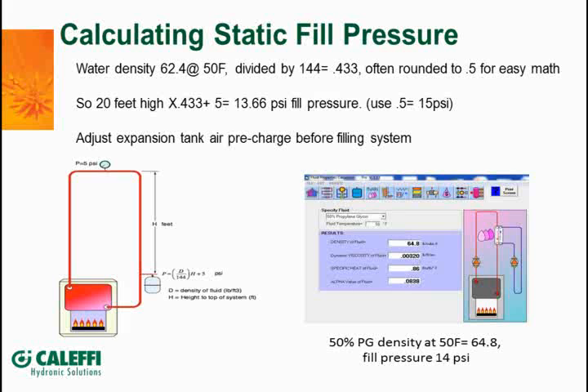You're not using the pump. Your circulating pump isn't putting the pressure in the system. It's the water or the fluid that you pump or pipe into the system that is giving you the static fill pressure. So how much do we need in the system? Well, we want to always have about 5 pounds pressure at the highest point in the system. So let's say that we've got a 2-story house example here we'll use. And we always want to have about 5 pounds pressure at the highest point.